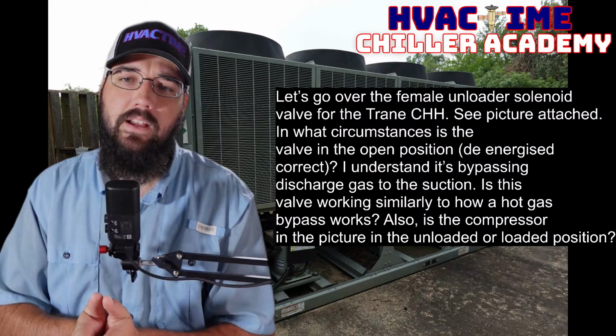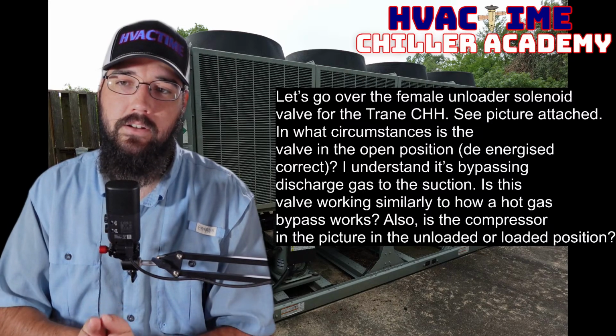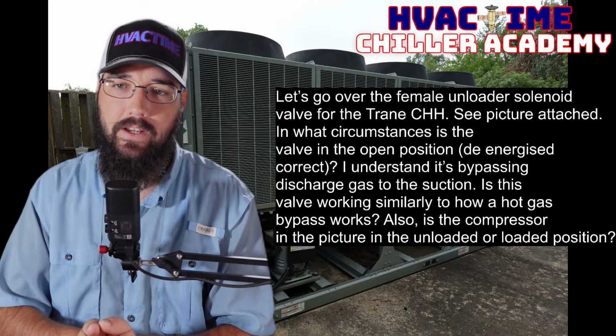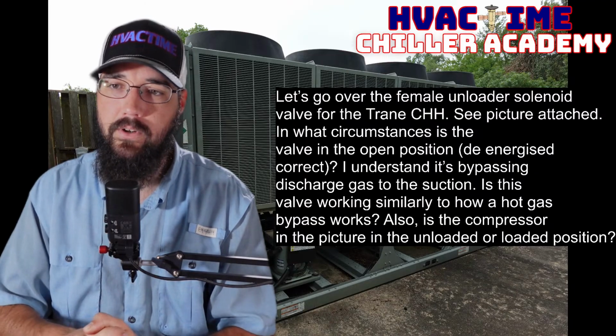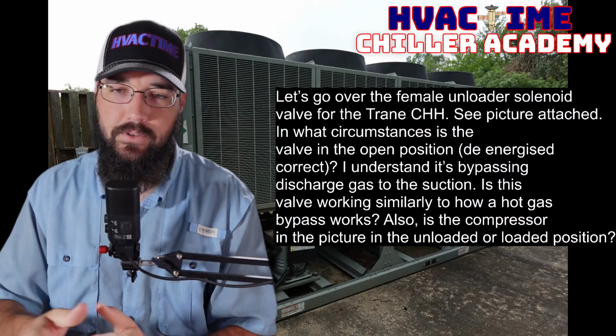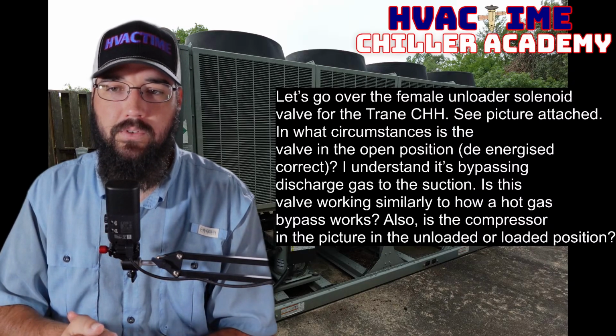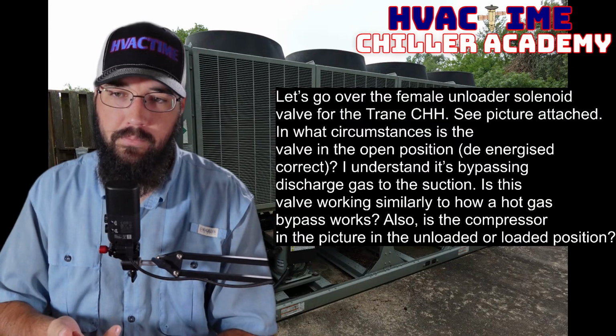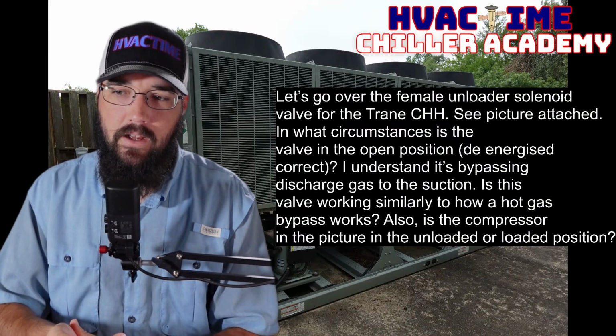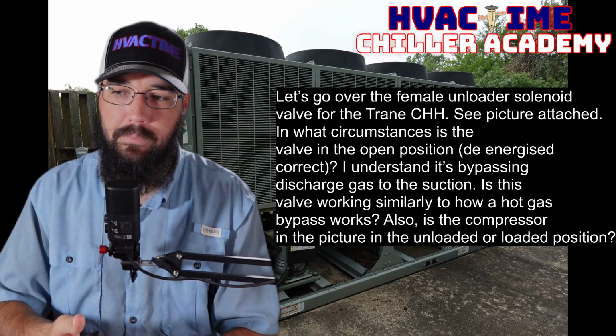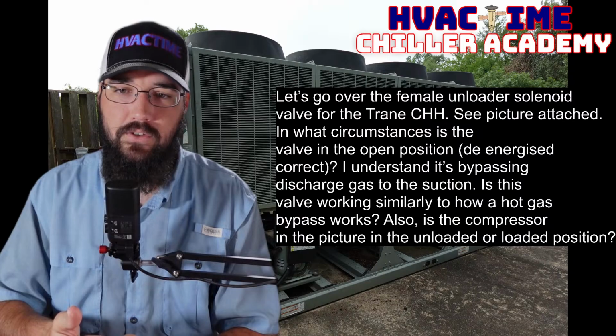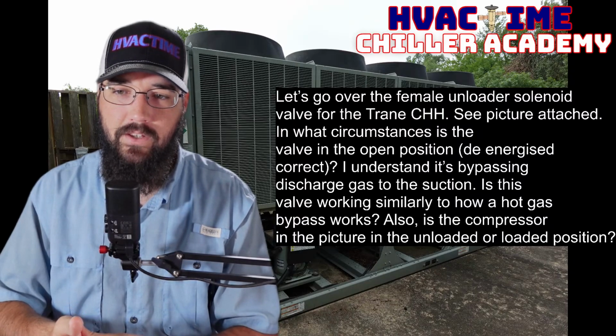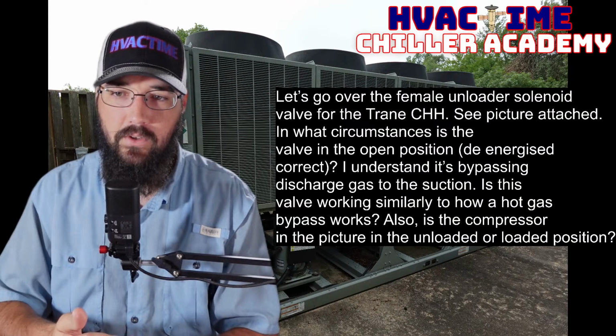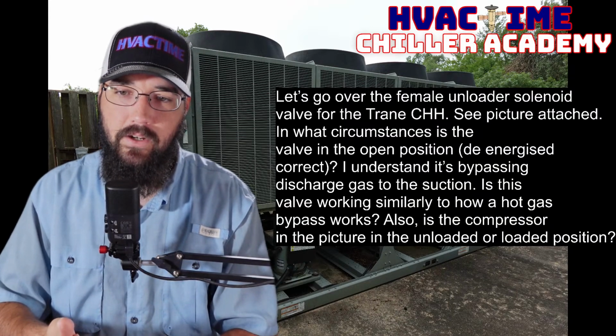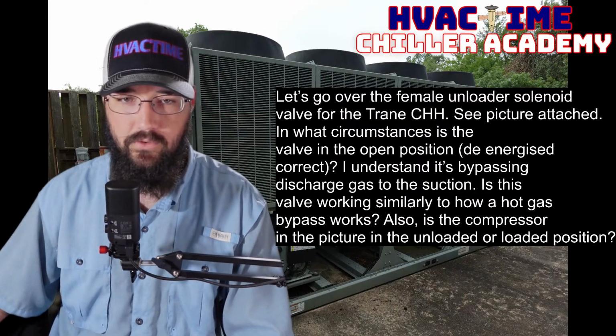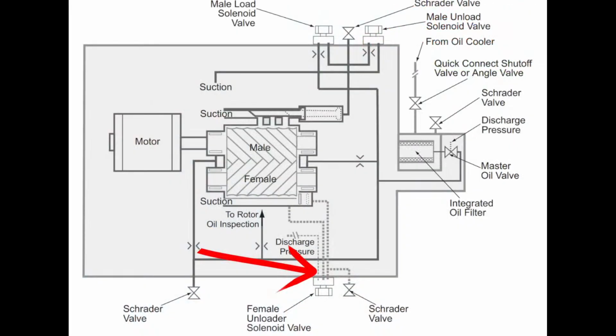Okay. Let's go over the female unloader solenoid valve for the Trane CHH, so Trane screw compressor. See attached picture, which we'll get to in a moment. In what circumstances is the valve in the open position de-energized? I understand it's bypassing the discharge gas to suction. Is this valve working similar to how hot gas bypass works? Also, is the compressor in the picture in the unloaded or loaded position? So that's going to be this one here.